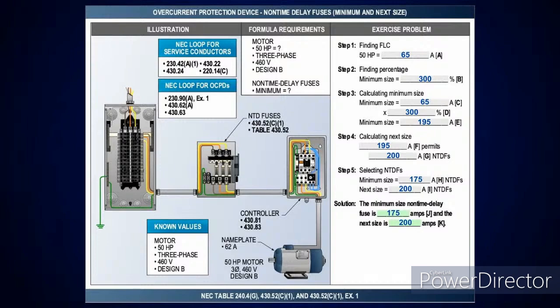So when I go over to my table, and I come down and I pick up my non-time delay fuse for a full take motor, it's going to tell you to take it at 300%. All right. So I'm going to take the 65 amps at 300%. That's going to give me 195 amps.